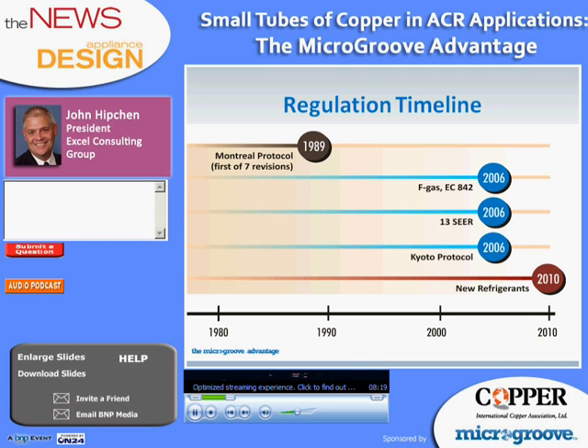The Montreal Protocol mandated a phase-out plan for CFCs, which are chlorofluorocarbon refrigerants, and they were mandated to phase out by 1995. This covered refrigerants like R12 that are no longer used. HCFC refrigerants, and those are hydrochlorofluorocarbons, were allowed as transitional replacements until HFC refrigerants are fully implemented. And HFC stands for hydrofluorocarbon, and this family of refrigerant does not have chlorine. And chlorine being the problem element, which has been linked to the depletion of our ozone layer.